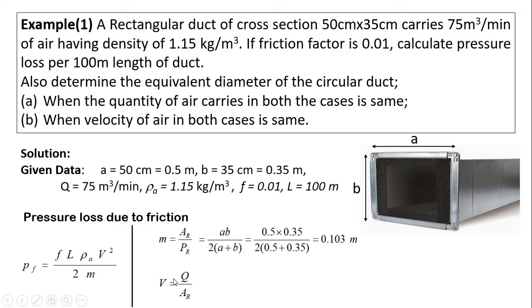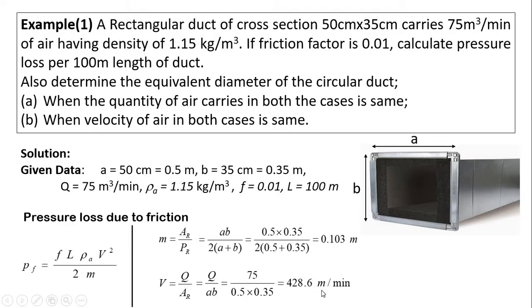Now we calculate the velocity of air flowing through the rectangular duct. Velocity v = volume flow rate Q divided by cross-sectional area a × b. Q = 75 m³/min and area = a × b. By putting the values we get velocity = 428.6 m/min. Since Q is in m³/min, velocity is in m/min. Dividing by 60 gives velocity = 7.143 m/s.